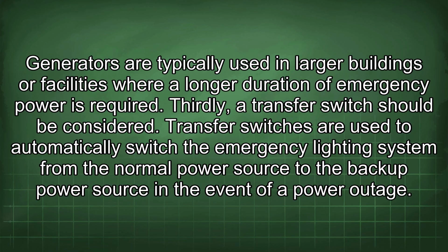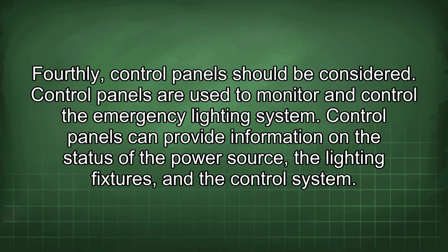Thirdly, a transfer switch should be considered. Transfer switches are used to automatically switch the emergency lighting system from the normal power source to the backup power source in the event of a power outage. Fourthly, control panels should be considered. Control panels are used to monitor and control the emergency lighting system. Control panels can provide information on the status of the power source, the lighting fixtures, and the control system.